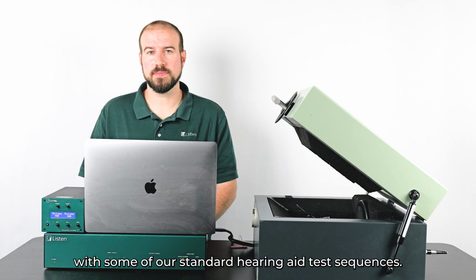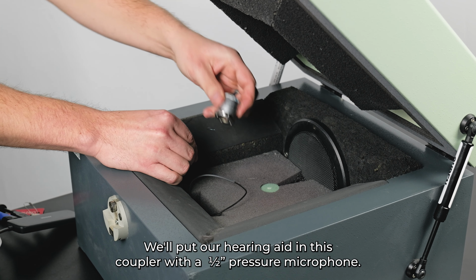It's a little more involved than something like a loudspeaker measurement because hearing aids have some unique test requirements. For a start, we need an anechoic test box. This one's a B&K 4232, but you can use anything similar. It has a speaker integrated inside, which we'll play our test signal out of. We'll put our hearing aid in this coupler with a 1/2-inch pressure microphone.